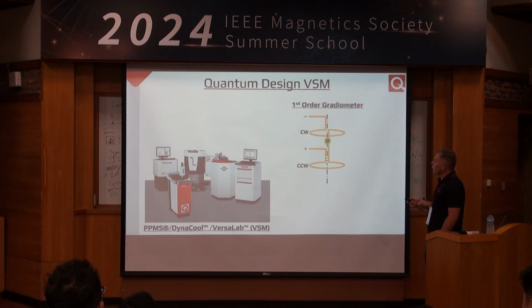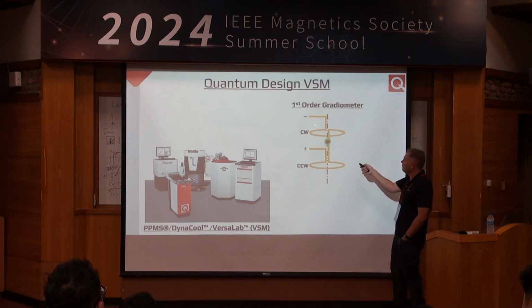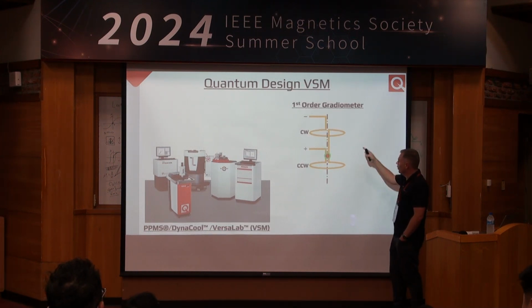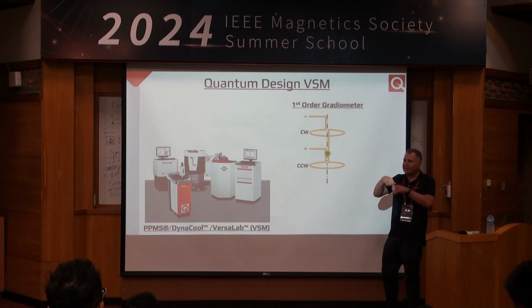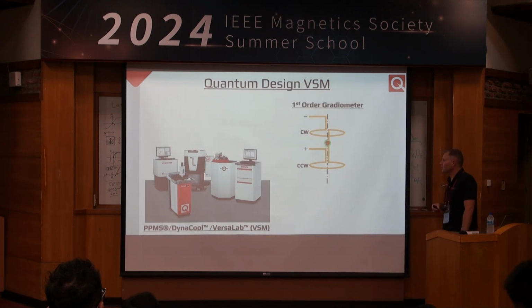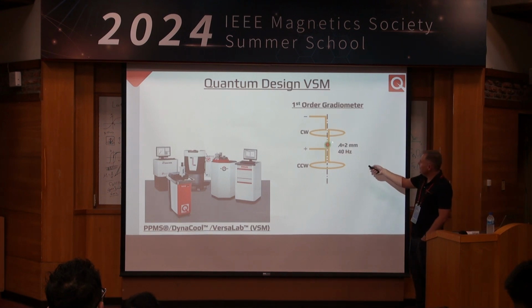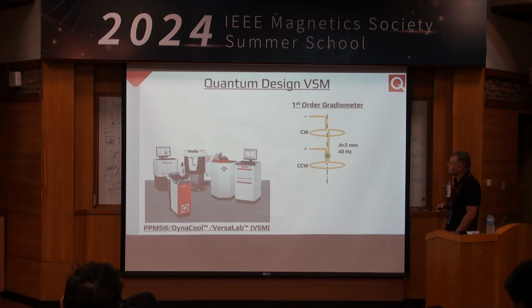So we've got a first-order gradiometer. That's just a fancy way of saying we've got a bunch of clockwise windings here and counterclockwise windings here. I only show a single coil in each of these. There's actually many, several hundred in each. Showing the sample vibrating between them, kind of slow so you can see it. Typical amplitudes are on the order of 2 millimeters and a 40 hertz frequency here.